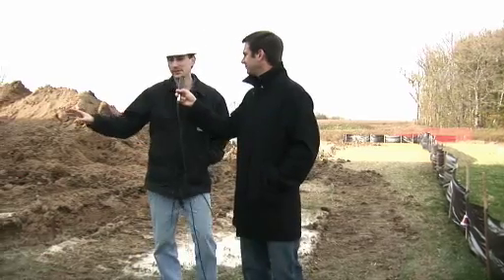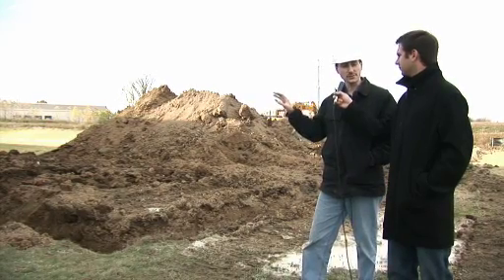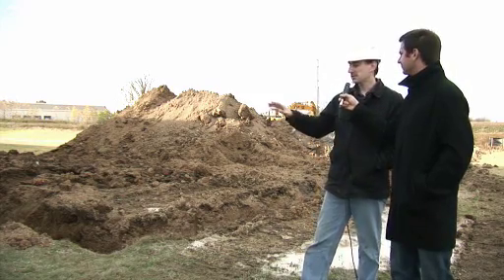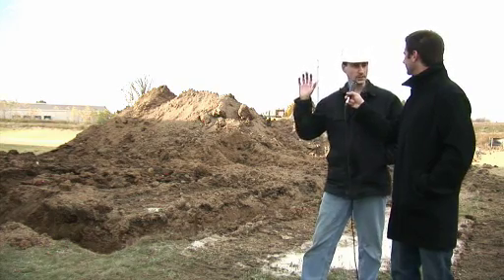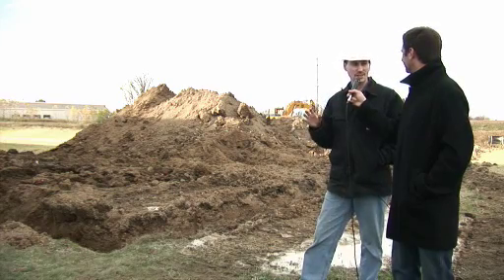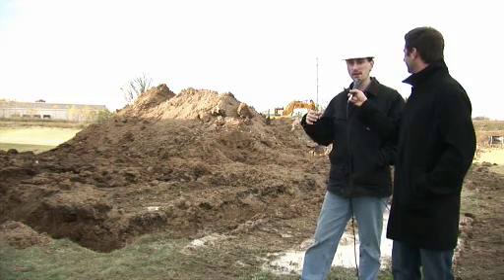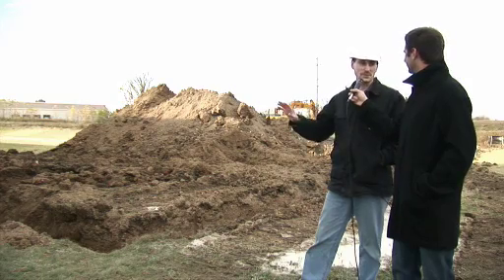Oh, that's great. And what's going on over in this area? Basically over here, the manholes and the trench line, that's all Board of Water and Light. This section here is all our pads. That's going to include our generator pads, our transformer pads, and our primary switch pads. In addition, we're doing all this excavation because it's all underground. When we go into the building, it's going to go through the foundation, come into our transfer switches and everything like that. Being all underground, again, it's very stable and nobody can mess with it. You don't have to worry about equipment moving around in the future and pulling down a piece of conduit or anything like that. Basically, we want to put it in once, never mess with it again.